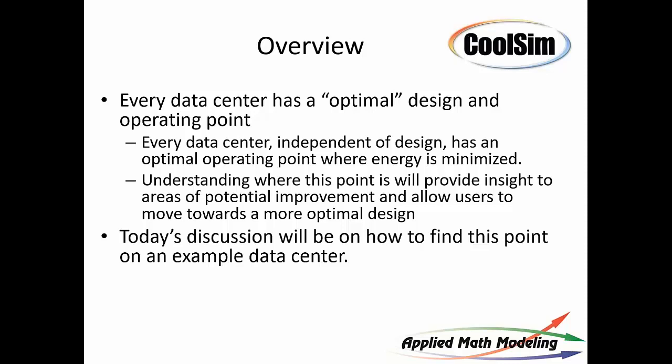Now, I need to preface this by saying data centers are ever-changing. They're actually transient environments. In other words, they're all changing all the time. Equipment's going in, equipment's going out. So the data center is a very dynamic place, and we're going to be modeling it as a steady-state environment. And the reason you do that is to give you more information than you have without doing that. Specifically, you need to understand where that optimal operating point is so that you can get as close to it as possible for optimization of energy. And with the cost of energy the way it is, this is becoming more important every day.